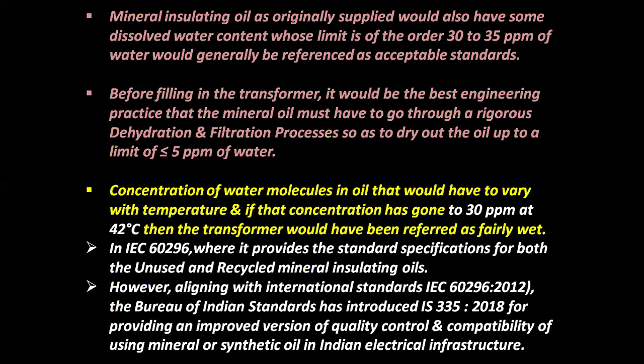Mineral insulating oil, as originally supplied, would also have some dissolved water content whose limit is of the order of 30 to 35 ppm, parts per million of water, which would generally be referenced as acceptable standards. Again, I repeat, the limit is of the order of 30 to 35 parts per million of water.